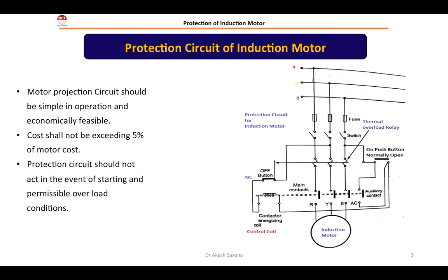Protection of induction motor. The three-phase supply is given to the induction motor through various elements such as fuse, switch, contactors, and thermal overload relay. The control circuit of the contactor consists of an energizing coil, start and stop buttons. The start push button is normally open, while the stop button is normally closed.